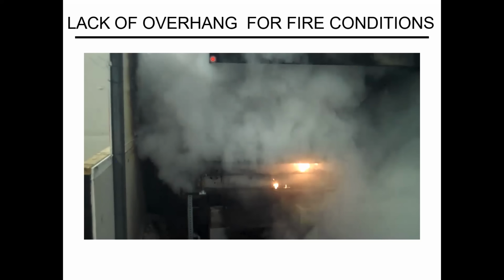Typically when you're designing a hood system, I think right here is just about the 2-foot mark. If you're within 18 inches of a wall, you really want to expand that hood, because for safety, you're going to see it if you have a fire. And like I said, this is set up exactly like most restaurants you'll see, where they'll start pushing equipment out when it really needs to be 6 inches over.